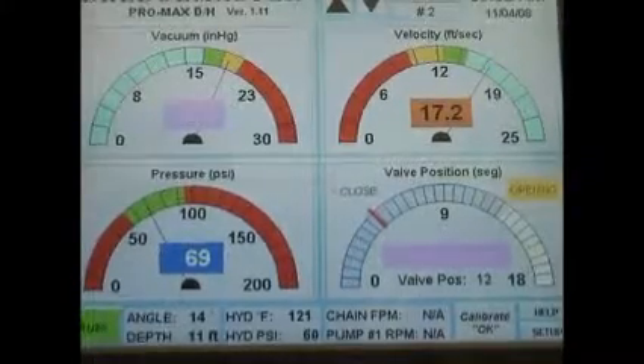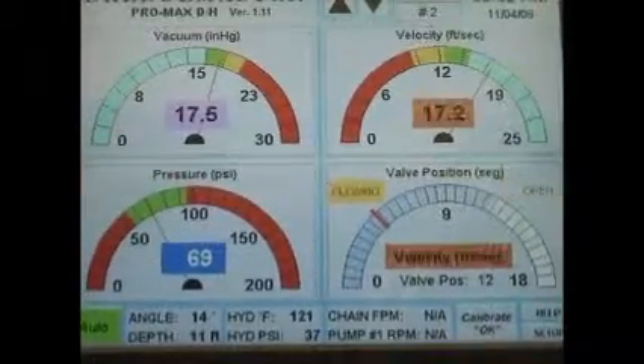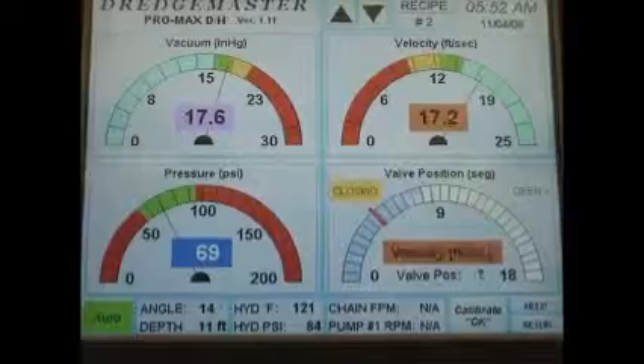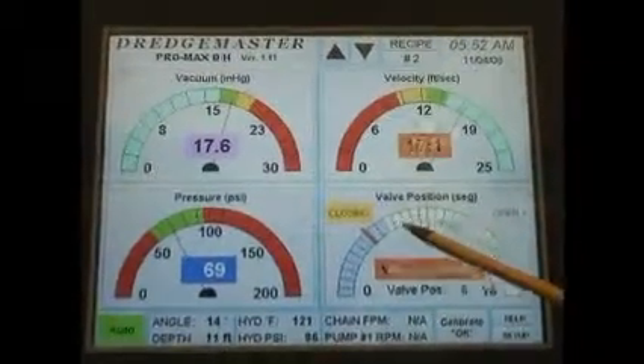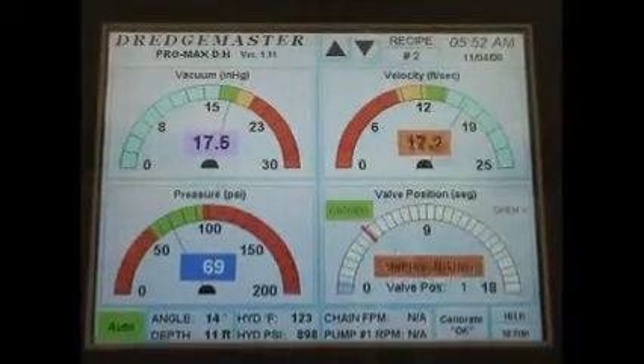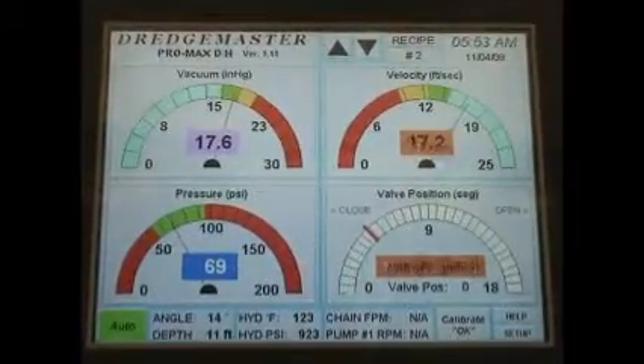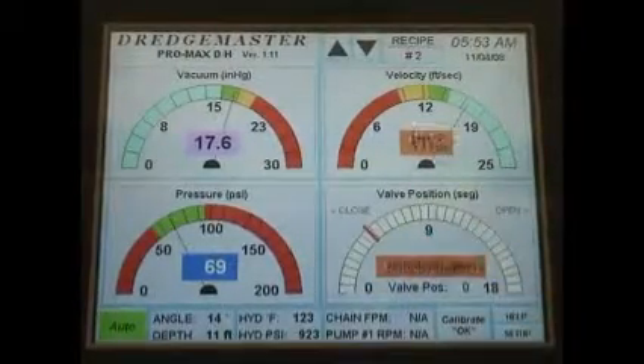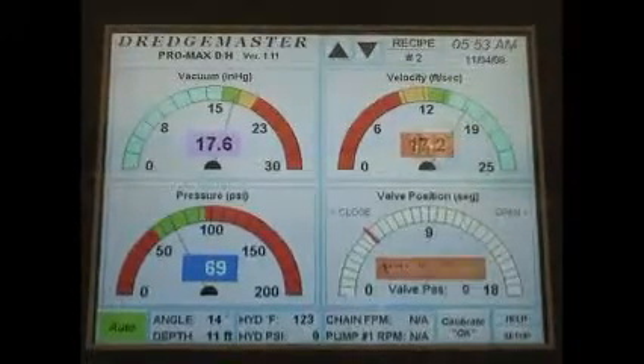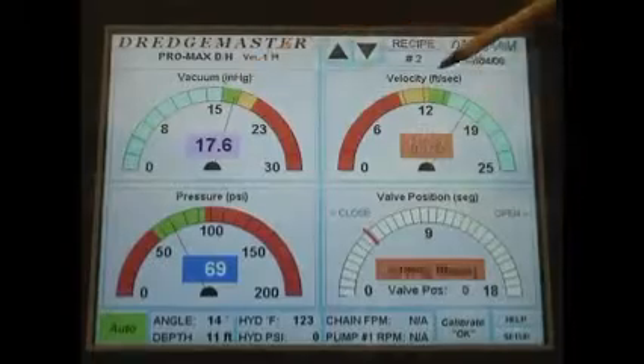The reason we have a 2-speed set point is the characteristics of a butterfly valve: when it first starts to open up, it lets very little water through until it gets about 25 to 30% of the way open. Then each segment that it opens or closes is more dramatic in the amount of volume being let through the butterfly valve. So that's one of the reasons we put the 2-speed in there, to allow water to be introduced in the freshwater pipe more rapidly, to make your vacuum or your velocity reactions a little bit quicker.